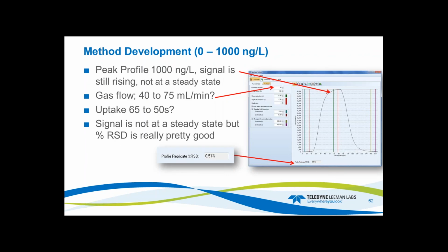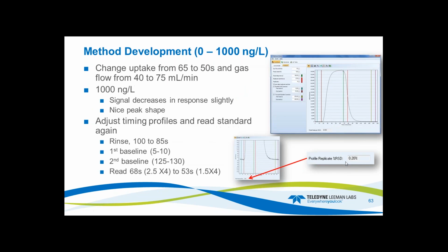Peak profile, here's a 1,000 nanograms per liter or 1 ppb. The signal's still rising, so it's not at steady state. So now what do we do? Let's get it faster, see what happens, move it through the system faster, hit a steady state. So I'll go from 40 to 75 milliliters gas flow uptake. I'm making it faster, so maybe I can cut back on the uptake. Signal profile is not steady, but the RSD is pretty good at 0.5%. And based on what I said earlier, that's not bad, but we can make it better.